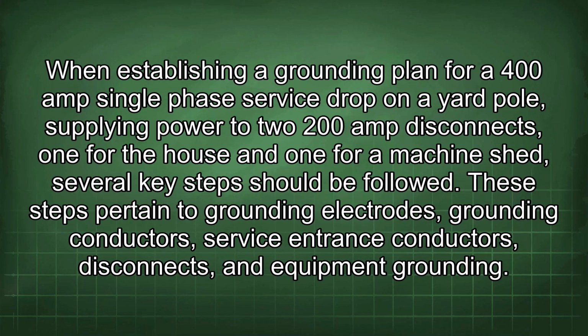When establishing a grounding plan for a 400 amp single-phase service drop on a yard pole, supplying power to two 200 amp disconnects, one for the house and one for a machine shed, several key steps should be followed. These steps pertain to grounding electrodes, grounding conductors, service entrance conductors, disconnects, and equipment grounding.